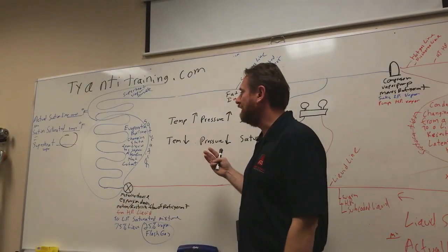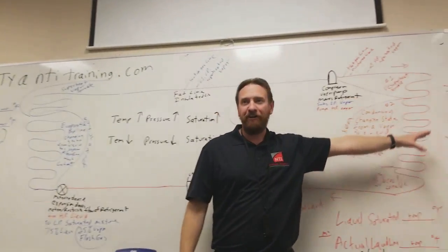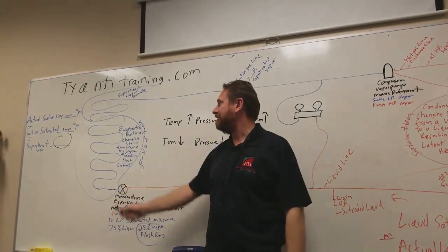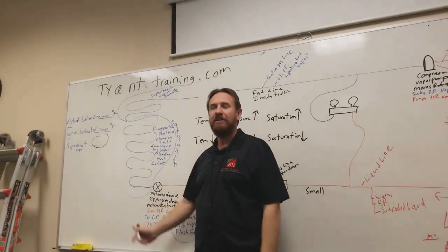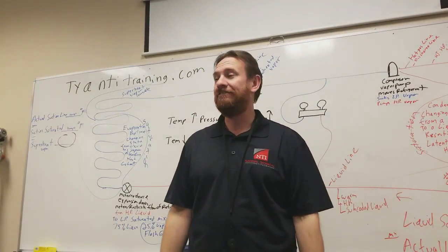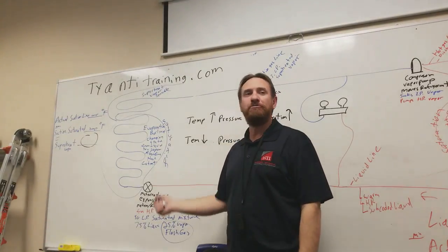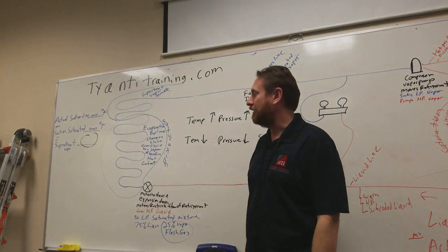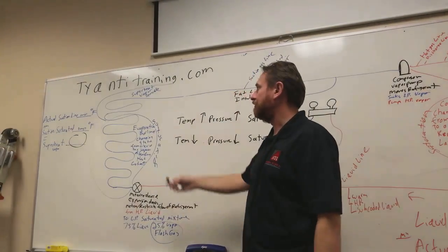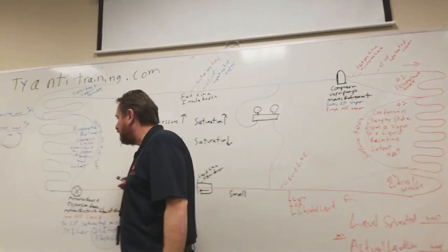The number 3 cause is the temperature's too low. Either the temperature outside falls too low, and I don't have enough pressure pushing through, or the temperature inside drops too low. Some people like to have the thermostat set at like 65, and that can cause it to freeze, along with the humidity in the air as well. You put a unit in Florida below 70, it's going to freeze quick. There's a lot of moisture in the air. And the last thing is a refrigerant restriction, something that's not getting through to here.